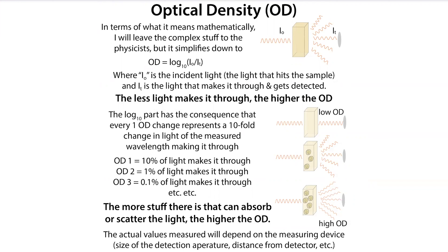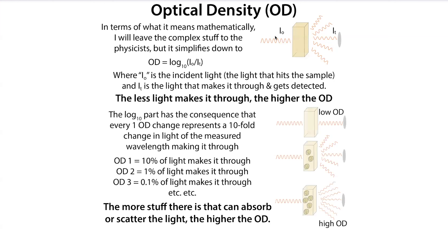Let's talk a bit more about what optical density actually means mathematically. It simplifies down to: OD equals log₁₀ of I₀ divided by IT, where I₀ is the incoming incident light and IT is the transmitted light that actually makes it through to the detector. The more light is lost, the higher the OD. Because of the log₁₀, a change of one OD represents a tenfold change in the light making it through. So at an OD of one, 10% of light makes it through; an OD of two is 1%; an OD of three is 0.1%; and so on.